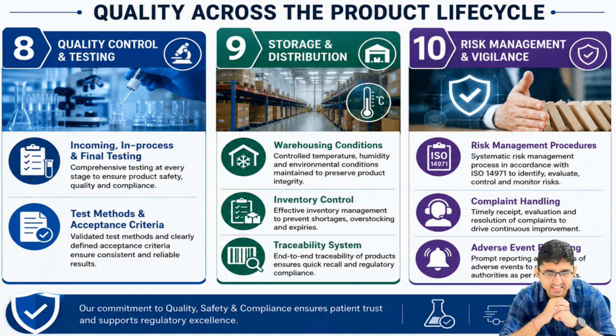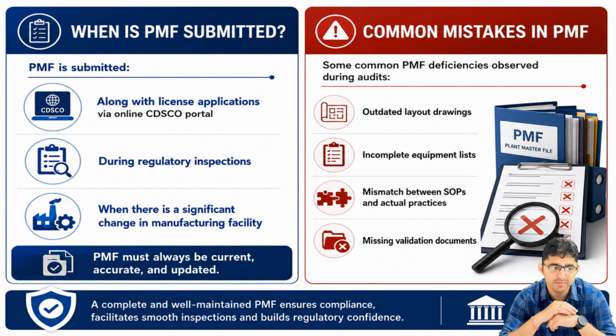So when is this PMF submitted? PMF is submitted along with the license application via the online CDSCO portal, and during regulatory inspections. And whenever there is a significant change in the manufacturing facility, you need to revise the PMF document and re-upload it in the portal.